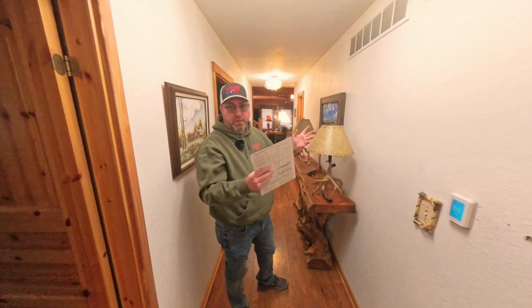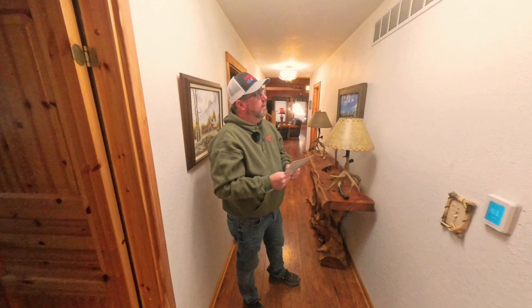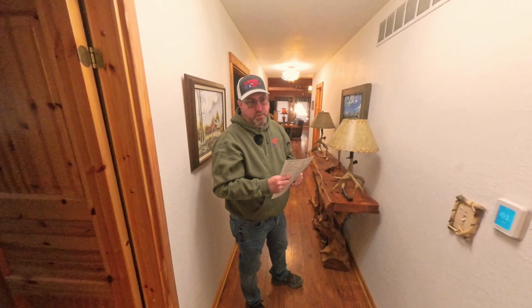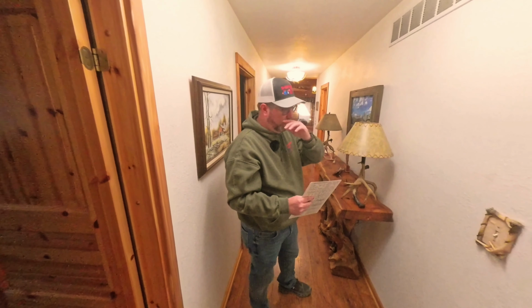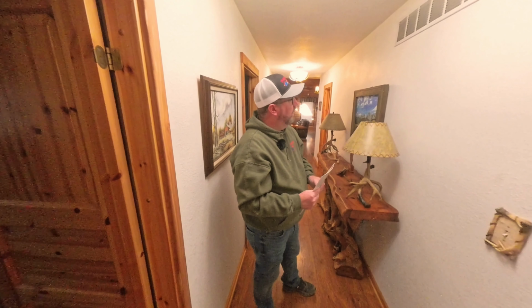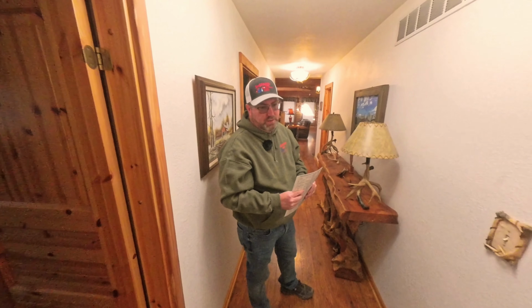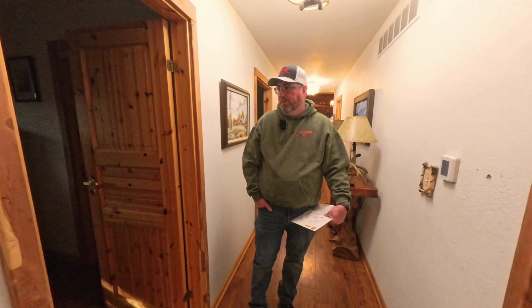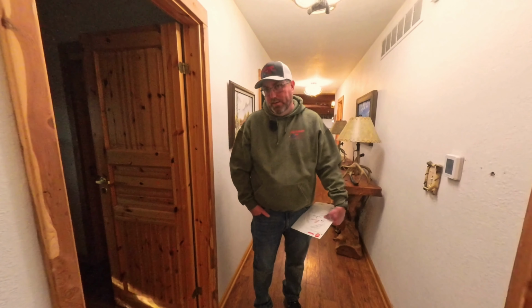We added up all the return grills in the house, found that it was short on return for the number of CFM that it needed to operate the system. So then we went to looking for solutions to add return to the home. You need to be able to move enough airflow through the system for it to work properly. We will hopefully not only just fix the customer complaints, but also have the system to where it'll work and not worry about failures due to improper installations.